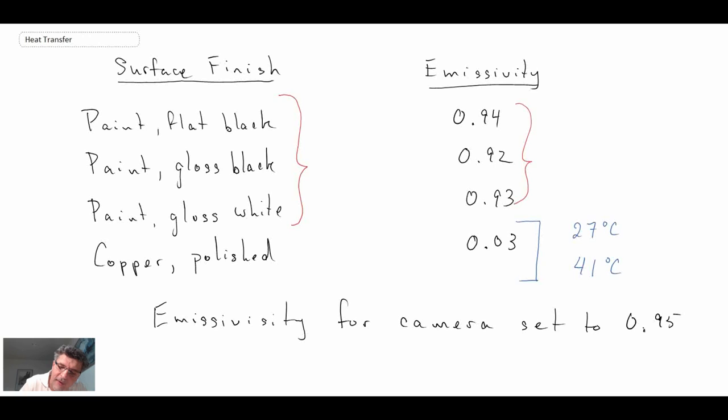So what does that mean? What that means is that if you wanted to use an infrared camera to measure the surface temperature of an object, you need to know what the emissivity of that object is. And so if you're measuring something such as copper, polished copper, chances are you're going to get an incorrect result if you do not adjust the emissivity accordingly in order to correspond to whatever the surface finish of that copper would be.